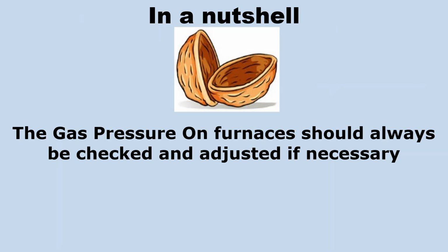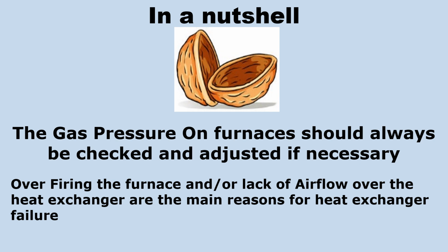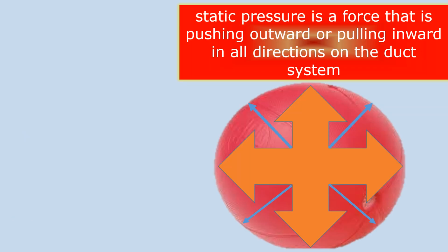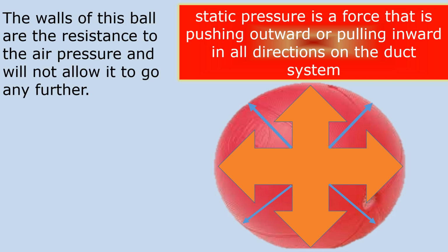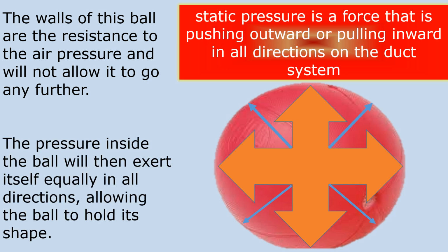In a nutshell, the gas pressure on furnaces should always be checked and adjusted if necessary. Overfiring the furnace and/or lack of airflow over the heat exchanger are the main reasons for heat exchanger failure. Static pressure is a force that is pushing outward or pulling inward in all directions on the duct system. The walls of this ball are the resistance to the air pressure and will not allow it to go any further. The pressure inside the ball will then exert itself equally in all directions, allowing the ball to hold its shape.